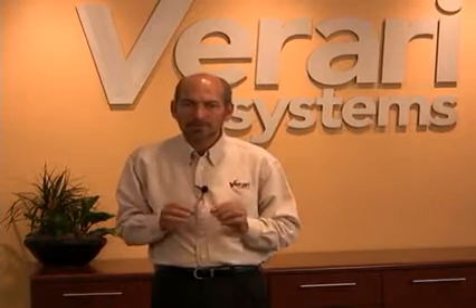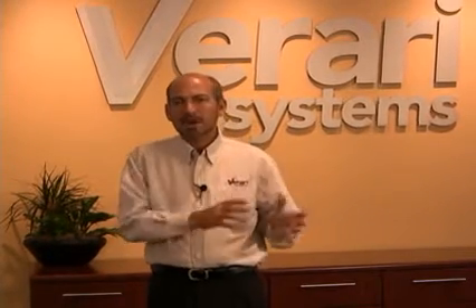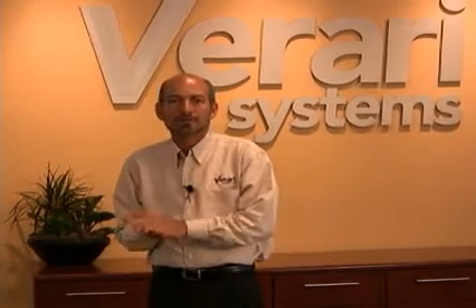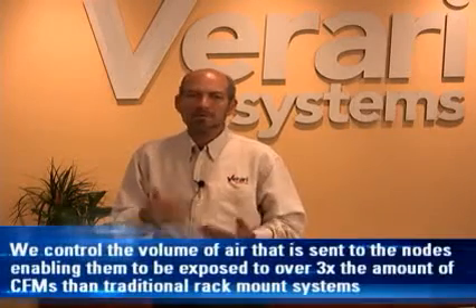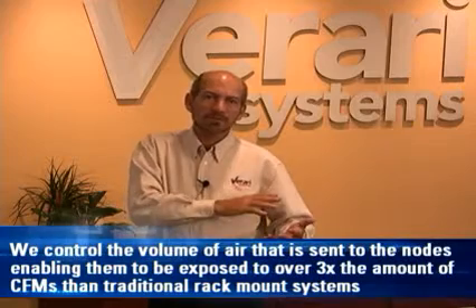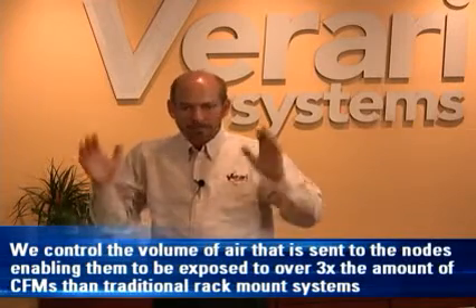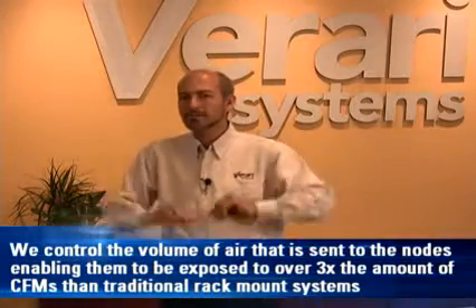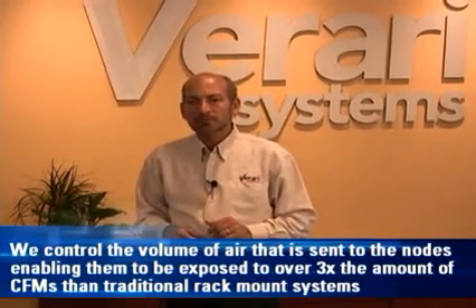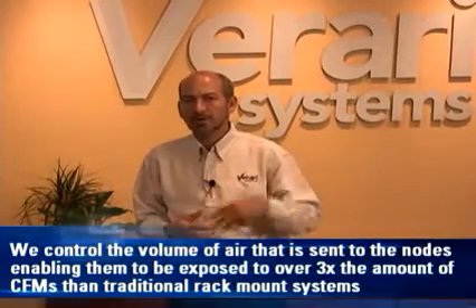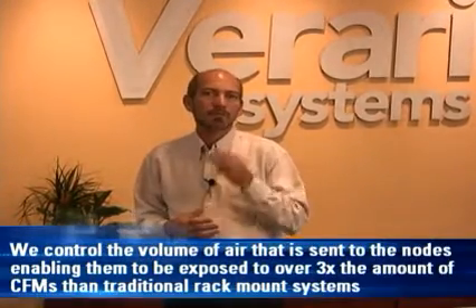Cooling is a function of volume more than it is of temperature. Delta T is derived from the amount of volume of air that moves across a given cooling component, so a heat sink or memory modules or hard drives. In our case, we control the volume. Compared to a typical 1U, which uses about 30 CFMs of air, our system within the same data center providing the same amount of air, will wind up being exposed to over 100 CFMs of air. Right off the bat, we're dealing with 3 times the airflow, 3 times the volume of air to work with.